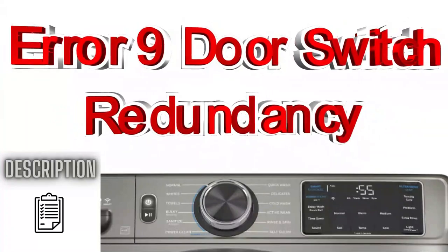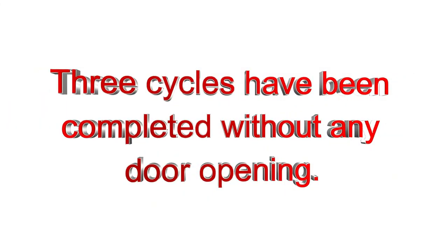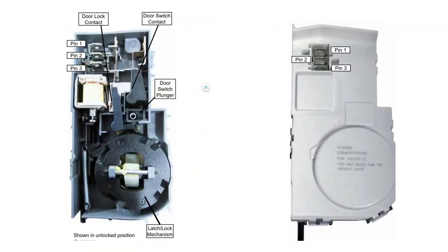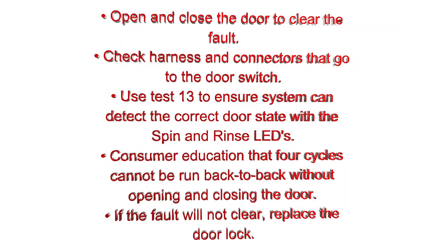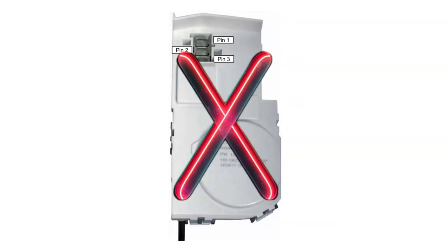Error 9, door switch redundancy. Three cycles have been completed without any door opening. Open and close the door to clear the fault. Check the harness and connectors that go to the door switch. Use test 13 to ensure the system can detect the correct door state with the spin and rinse LEDs. Consumer education: 4 cycles cannot be run back to back without opening and closing the door. If the fault will not clear, replace the door lock.